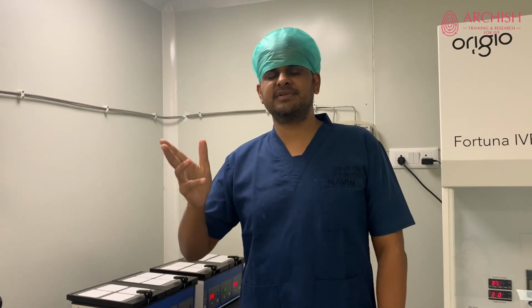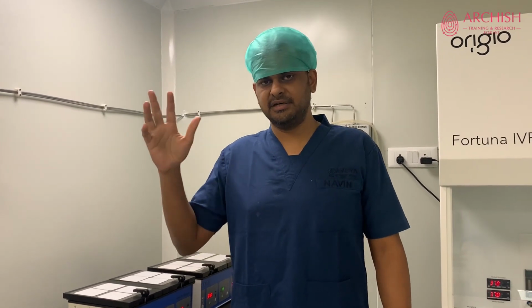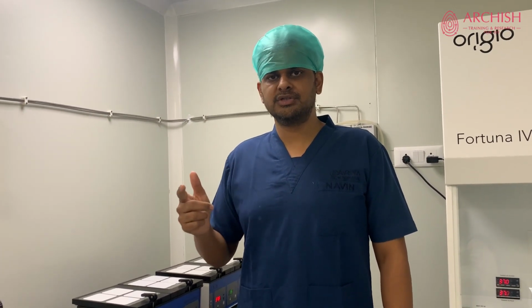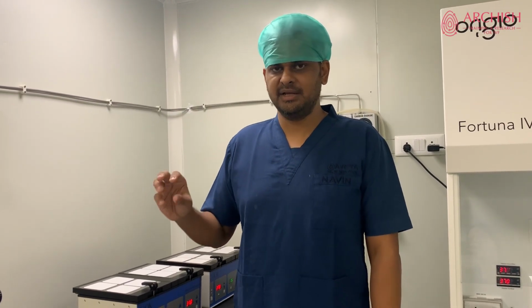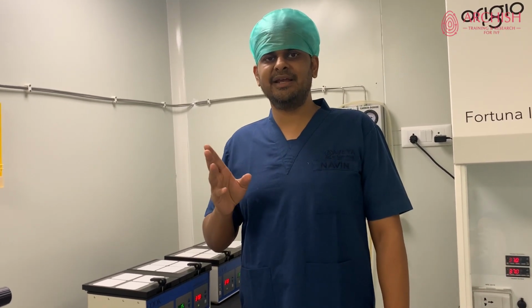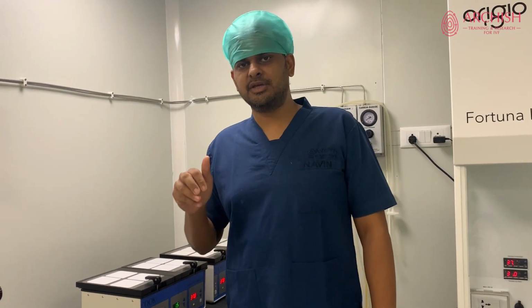Similarly, the big box incubators - these are the working incubators that we keep reopening every day, probably 10-20 times a day. So even in those incubators, you have water content and CO2. It's important to check CO2, temperature, and water in these big box incubators as well. Once you have finished this, it's important to document it, and at the end of the month, analyze if there has been any spike or dip in the QAQC parameters.